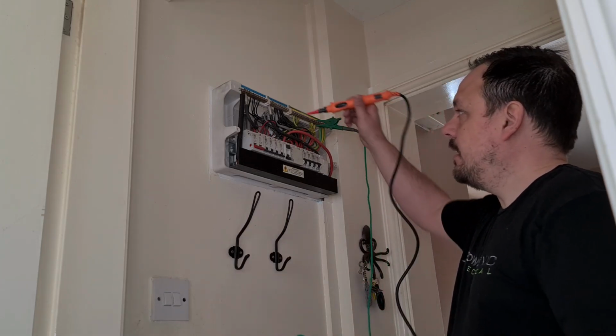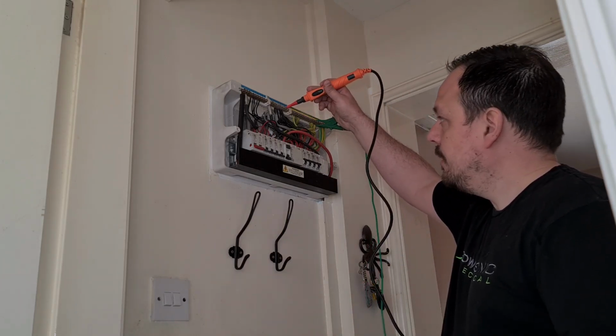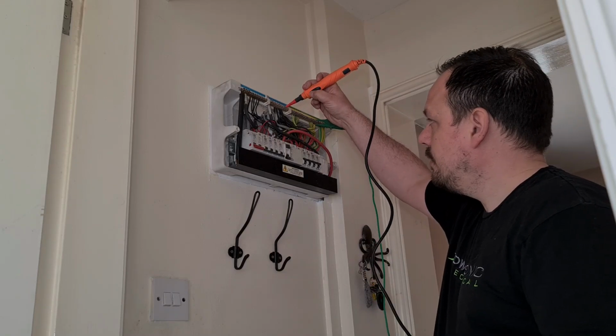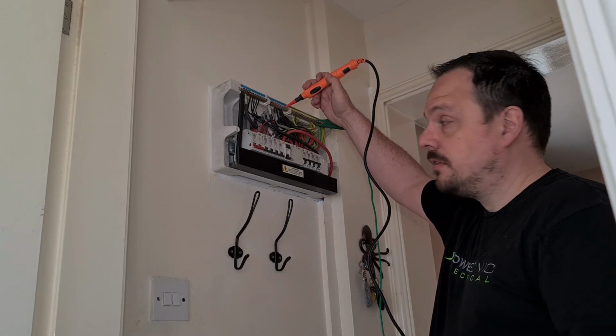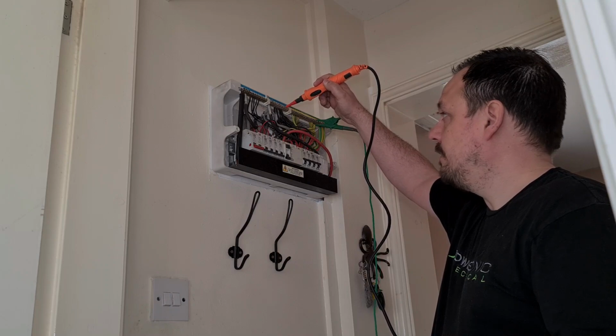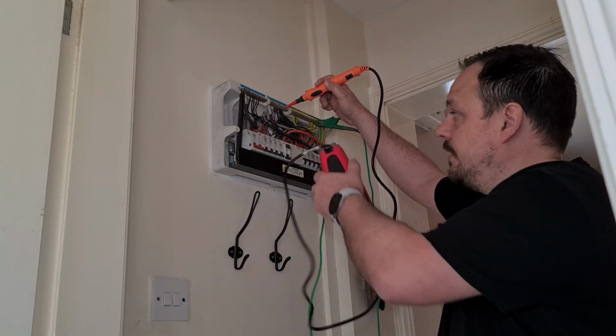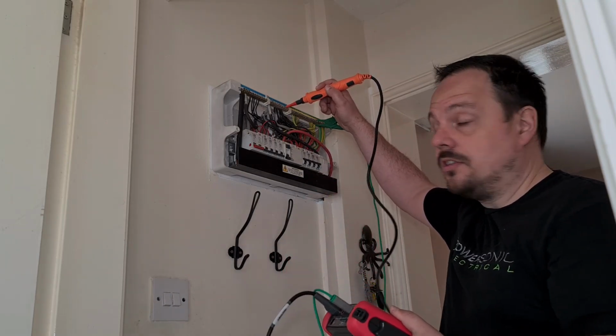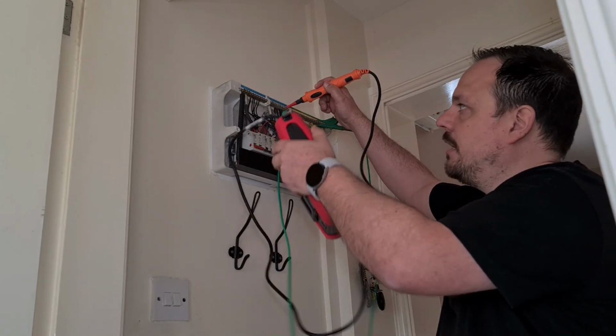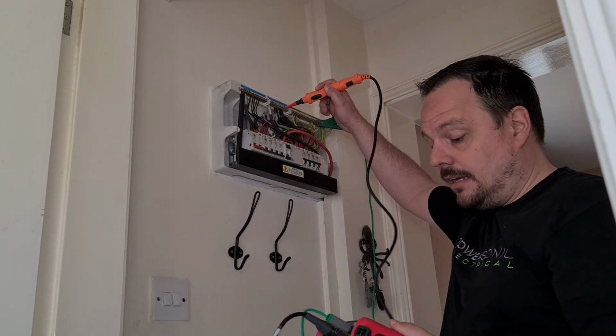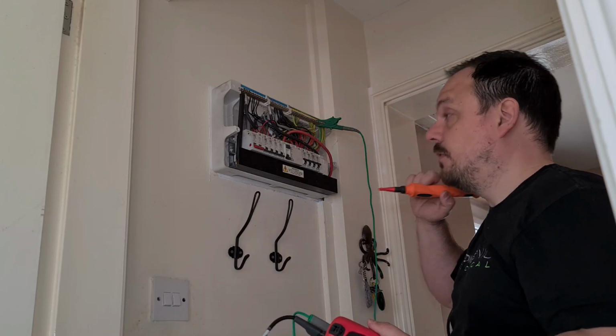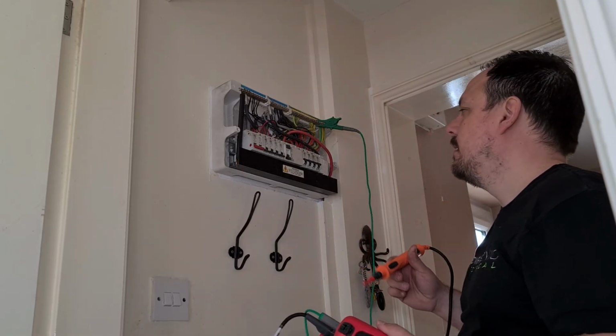And again, you can repeat that process between the CPC and the neutral. Same principle. Obviously this is the neutral bar for these circuits. The RCD that feeds into that is in the off position, so there's no connection between the neutral bar for the lighting circuits. And again, it's giving a reading of over 499 megohms.